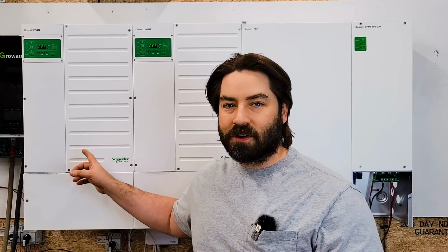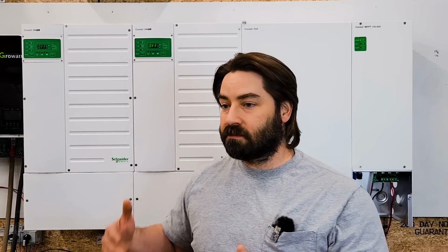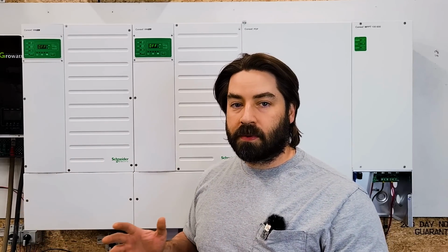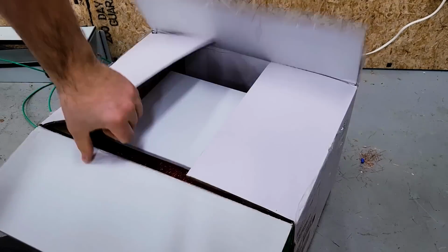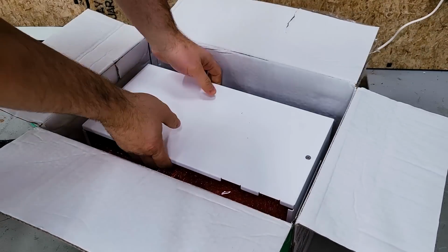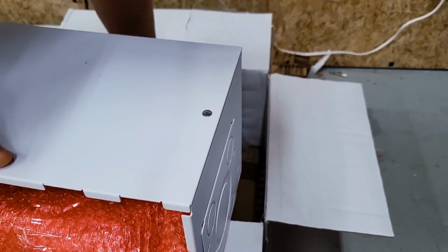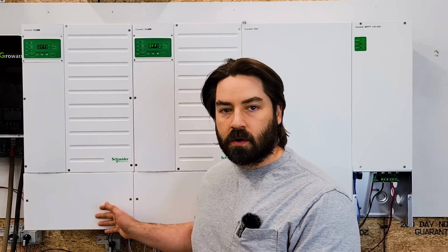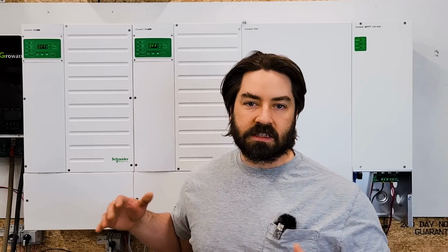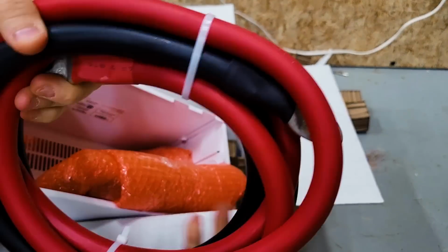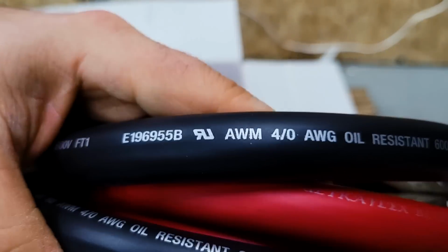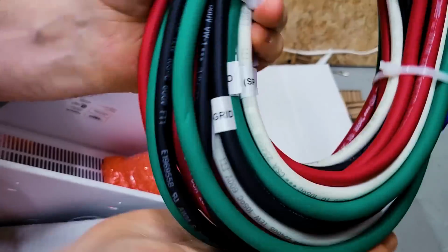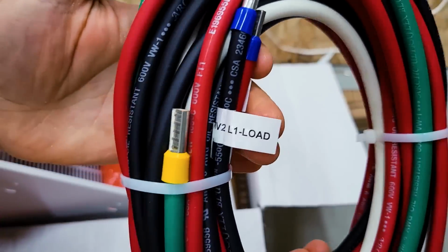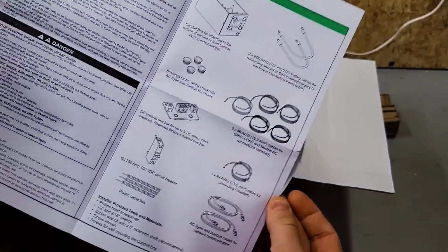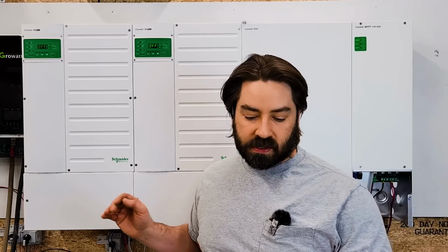After the inverter is mounted and secured, you could certainly make all your own wiring. But I bought Schneider's expansion kit for 2 or 3 inverters off of the PDP. That gives you this nice wireway. It's metal wireway. It's all UL approved. It's going to pass inspection very easily. But it also comes with the wires pre-labeled, the lugs pre-crimped on there. It makes for a nice quick installation, at least quicker than making up all of your own wiring. That kit is called the Conext Inverter Connection Kit, and here's the part number for it.